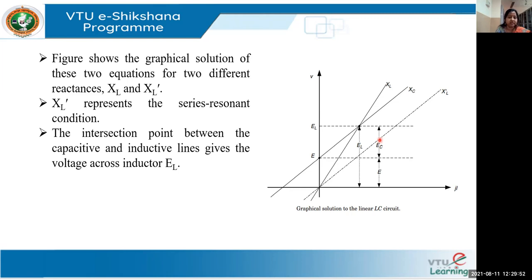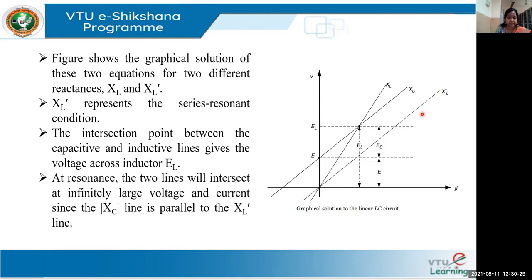When XL-dash represents the series resonant condition, you can see that XC and XL are effectively parallel. When they are parallel, they intersect at a very large value of voltage and current — the Y-axis is voltage and the X-axis is current. At that point of ferroresonance, the voltage and current are very high. That is how ferroresonance is visible with the help of the graphical solution.